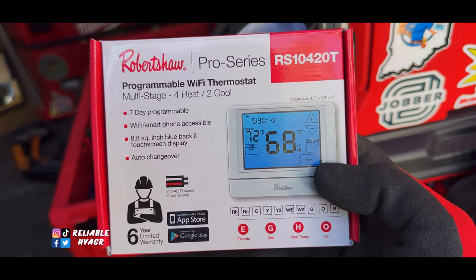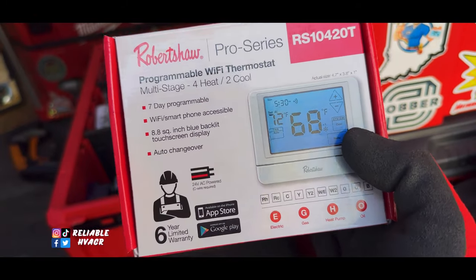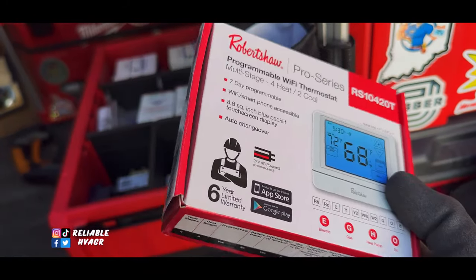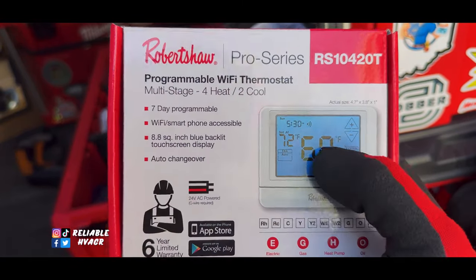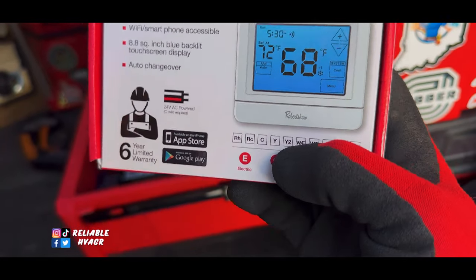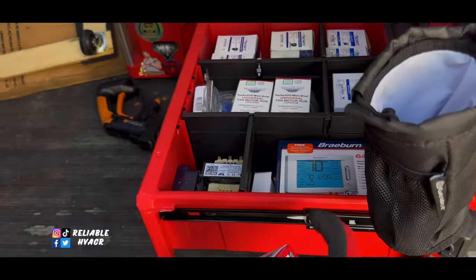We needed a two-stage. Do it the proper way. A lot of people around here do single-stage and put both Y1 and Y2 on one terminal. On the single terminal. But, we're going to do it the right way. Do two-stage. So, I carry a two-stage. I carry another one of these that's single-stage for some of those units that we run into. And, then I have the fancy one that has a sensor, but I'm not running the sensor.